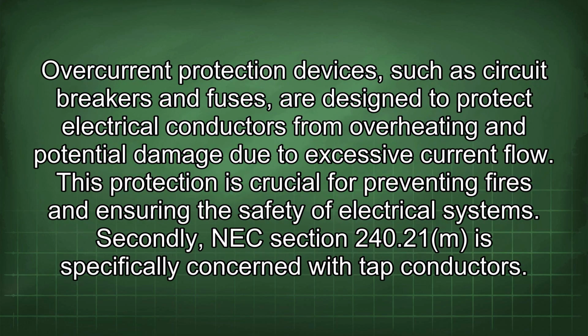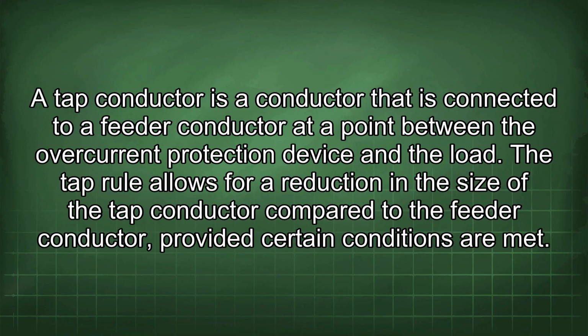Overcurrent protection devices, such as circuit breakers and fuses, are designed to protect electrical conductors from overheating and potential damage due to excessive current flow. This protection is crucial for preventing fires and ensuring the safety of electrical systems. Secondly, NEC Section 240.21 is specifically concerned with tap conductors. A tap conductor is a conductor that is connected to a feeder conductor at a point between the overcurrent protection device and the load. The tap rule allows for a reduction in the size of the tap conductor compared to the feeder conductor, provided certain conditions are met.